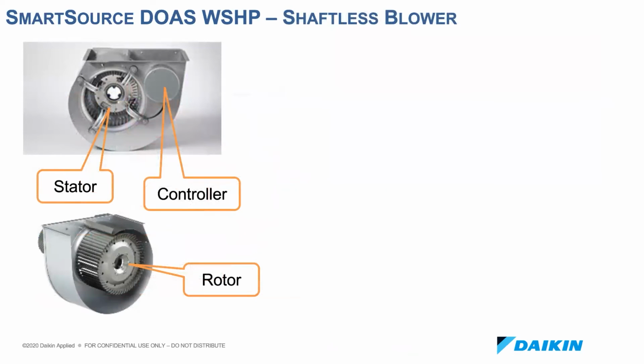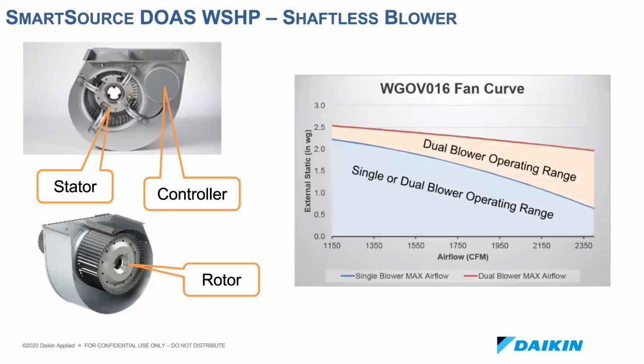Next is the new fan technology. The EC motor is integral to the blower assembly. The motor stator is fixed to the blower housing with the 4 legs you see in the upper picture. The rotor is attached to the hub of the blower wheel. And then the module you'll see attached to the outside of the blower housing is the electronic controller for the motor. Our units may have 2 of these blower assemblies depending on the nominal size.